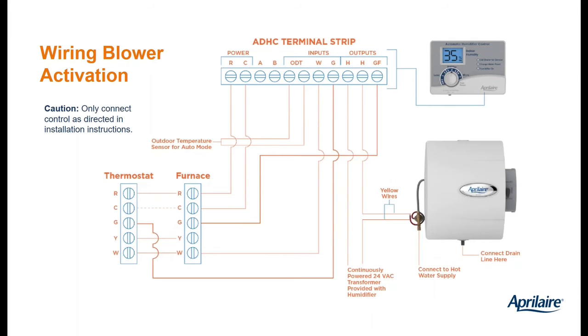Let's go back up to the humidistat. A and B we can skip. Don't have to worry about those. 2 terminals in the middle. That's where you're going to wire the outdoor temperature sensor to. So the outdoor temperature sensor has 2 conductor wire. It's no polarity. So 1 wire, 1 conductor goes to each of the 2 ODT terminals. 2 wires, 2 screw heads. Couldn't be simpler. Heck, we're almost done.